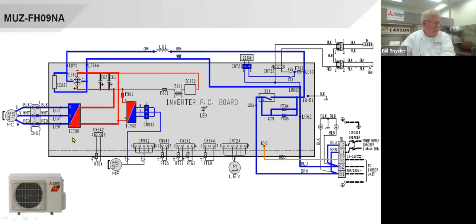This is an IC, which is inverter circuit. It's a power module. It could be labeled IGBT, which is the insulated gate bipolar transistor, or it could be IPM, which is intelligent power module. They're all the same. They're converting from 300 volts DC to the simulated three-phase AC going out to this motor compressor here, which is labeled as three-phase.